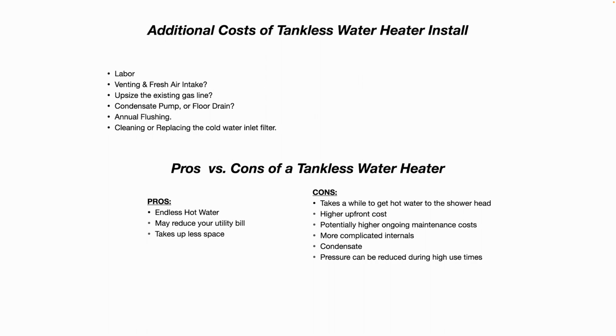Again, higher upfront cost. They're usually 3 times as expensive compared to a standard tank type water heater. And it's a higher labor cost, especially if it's a retrofit where you're switching from a tank type to a tankless. Potentially higher ongoing maintenance costs. Again, as we spoke about before, you got to flush them once a year, change or clean out that inline cold water inlet filter. And again, more complicated internals, more expensive repair parts. The repair parts may not be as readily available as they are for a tank type water heater.